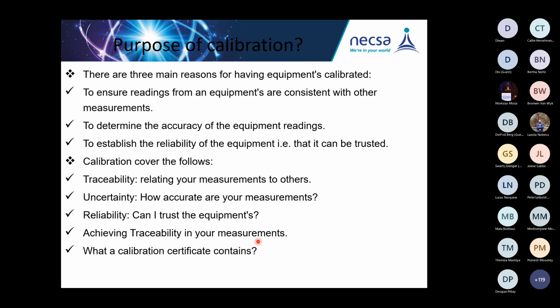And then we keep the certificate or the instrument in the cabinet until they come to inspect us. We're doing this for the benefit and for the safety of the radiation workers. A radiation worker can be anyone who is registered with the South African Bureau of Standards, wearing a TLD or any other field. People might also have access to a supervised area where there is radioactive material or a level of radiation. But in that case, they will be relying on the calibrated instrument.